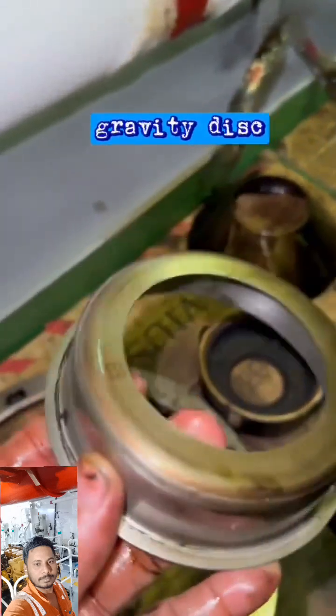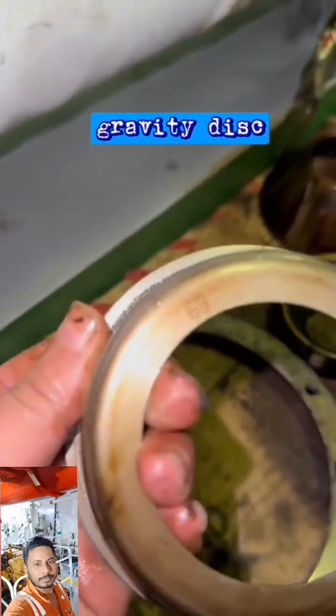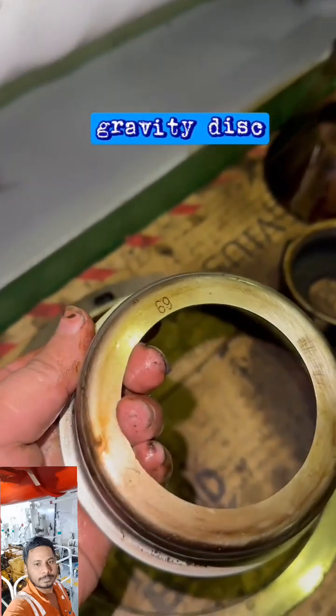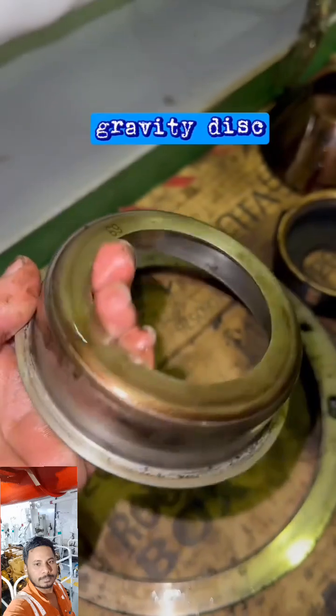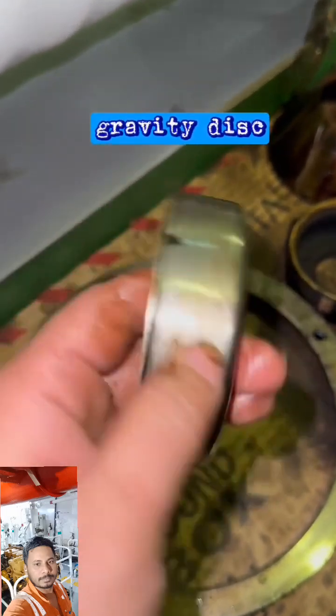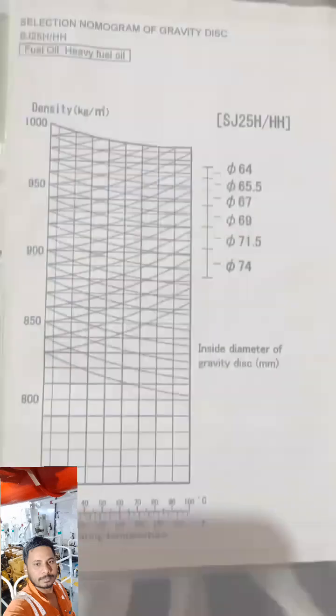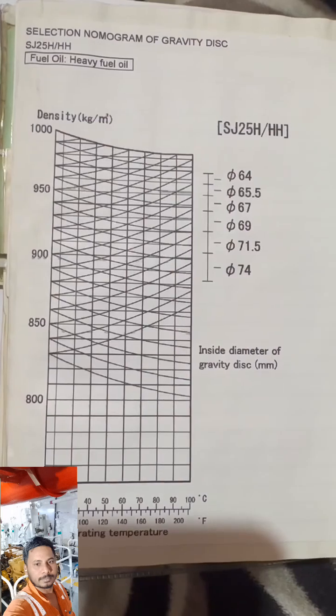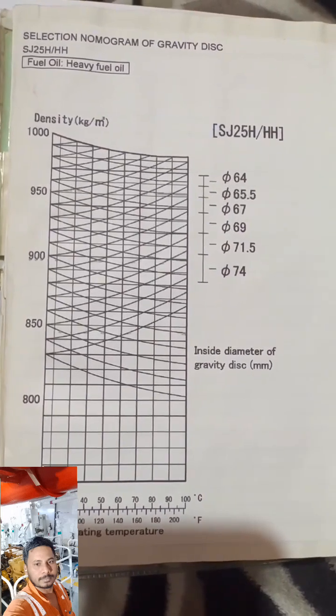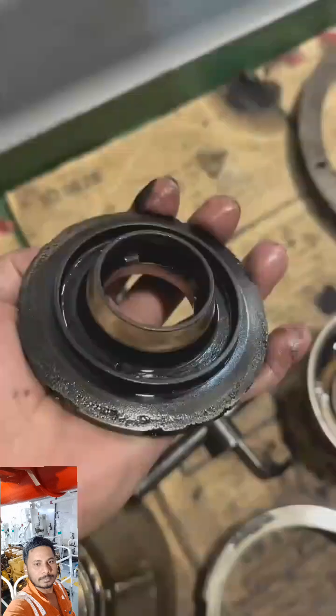Gravity disc. Used to maintain the correct interface between the oil and water. The purpose is to fit for purifying oil of different specific gravity. To determine the correct gravity disc, use the nomogram provided in the instruction manual.